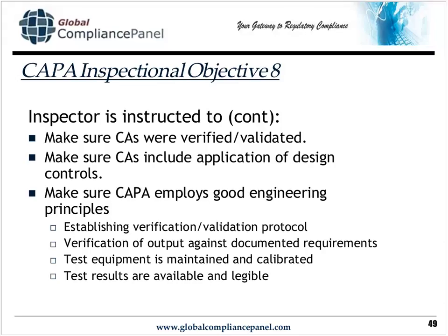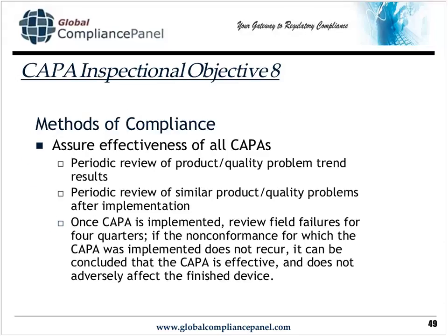Is there a protocol written before the actual test is performed? Is that protocol approved before the test is performed? Are there documented requirements in the protocol against which output is verified? Is the test equipment used, maintained, or calibrated? You've got to account for that in your validation protocols. And are the test results there? Are they available? And are they legible? Is it just a bunch of scribbles that are unable to be read?